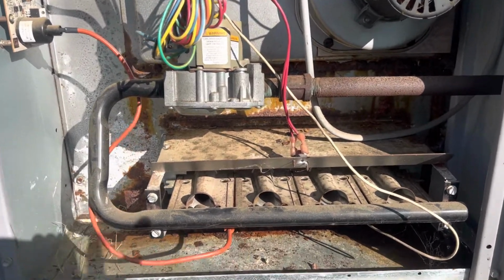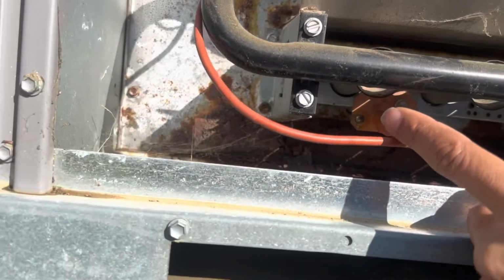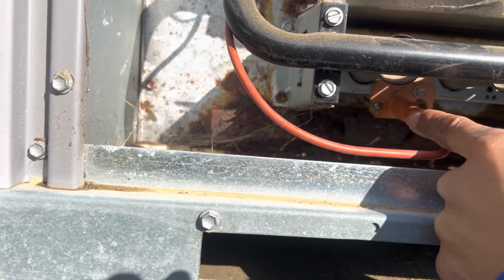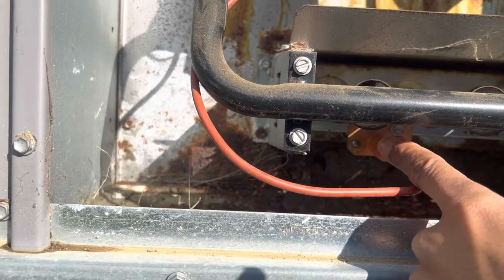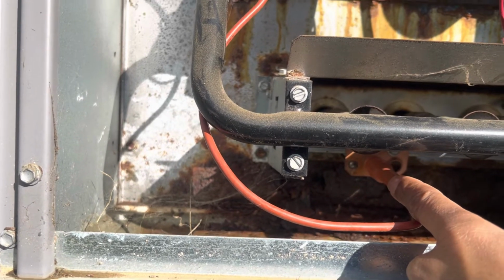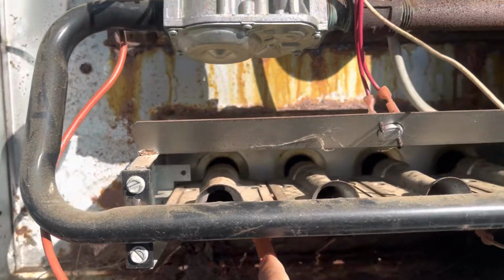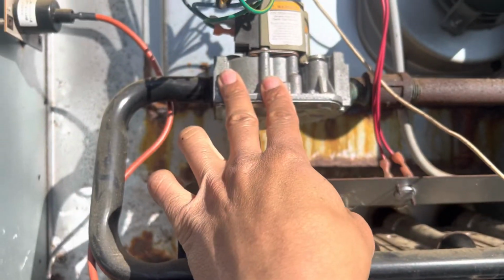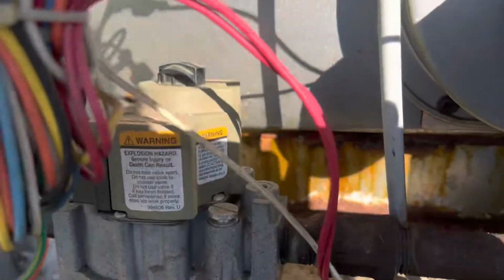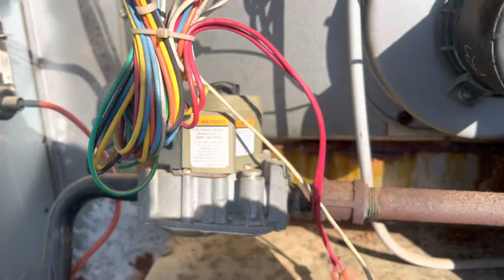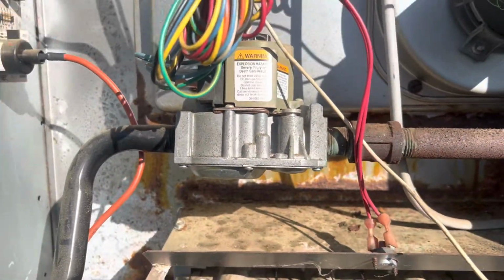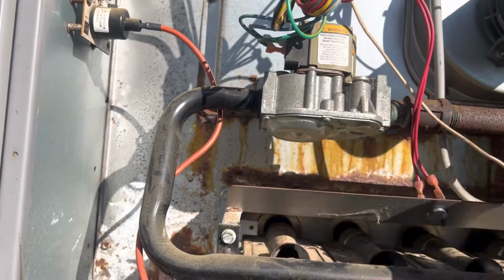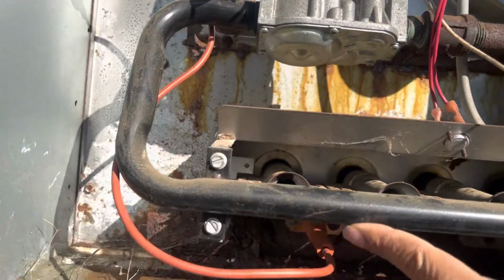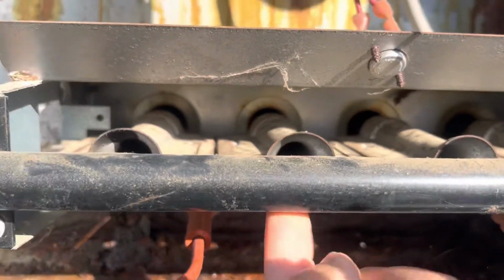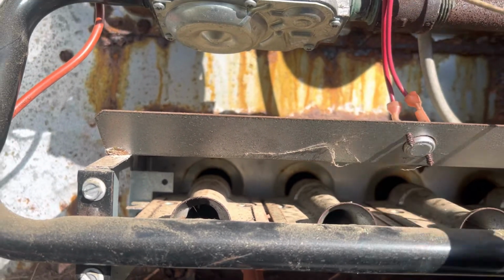to turn the gas. Well, if you have a spark ignition or a hot surface igniter, if it's a hot surface igniter, you're gonna see it glow. If it's a spark ignition, you're gonna hear it sparking, okay? Once that spark comes on, then the board is going to turn the gas valve on, okay? All right, so that gas valve is on. There's a little on-off switch there. When that gas valve comes on, gas is going to come from the meter into these orifices, and the gas is going to come on.